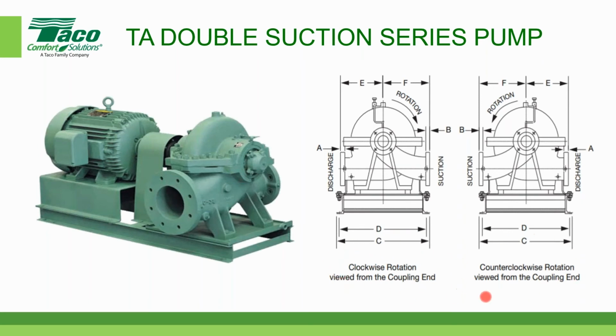Clockwise or counterclockwise, and that's from sitting on the coupling end or sitting on the motor. So sit yourself on the motor, look at the pump installed in your mechanical room, and make sure you order it clockwise or counterclockwise. They can be changed in the field, but it's a PIA, okay, it's a big PIA. Trust me on that. You got to replace the gasket and flip things around. It's not an easy setup to do.